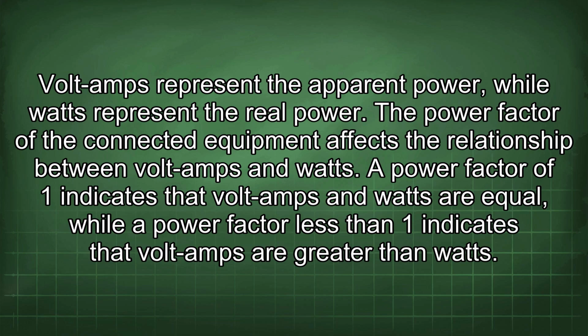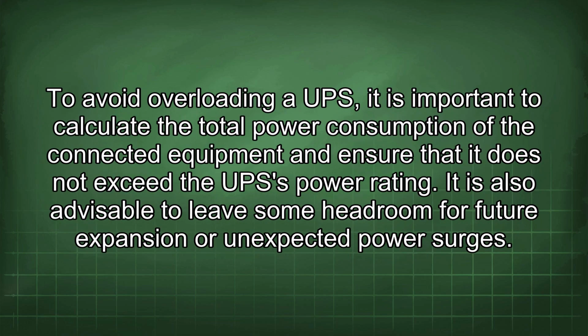The power factor of the connected equipment affects the relationship between volt-amps and watts. A power factor of 1 indicates that volt-amps and watts are equal, while a power factor less than 1 indicates that volt-amps are greater than watts. To avoid overloading a UPS, it is important to calculate the total power consumption of the connected equipment and ensure that it does not exceed the UPS power rating. It is also advisable to leave some headroom for future expansion or unexpected power surges.